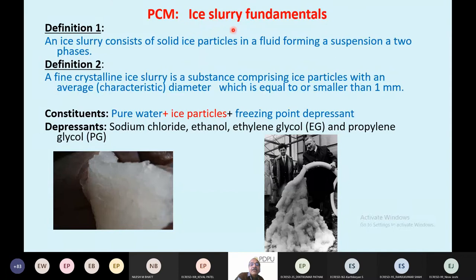Ice slurry is nothing but a mixture of very small ice particles, a depressant, and water. Normally when temperature goes low, water freezes, but with ice slurry, due to the depressant, you can achieve a semi-liquid slurry form at minus 10 or minus 15 degrees, depending on how much depressant is added.